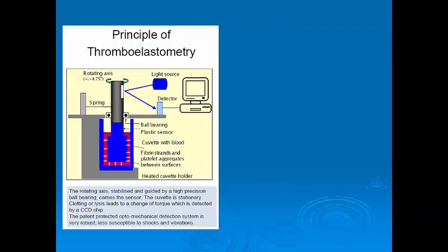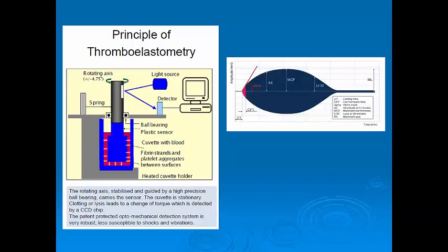A sample of the citrated whole blood is placed in a small cuvette. Reagents are added to activate the clotting process, and then a rotating pin is immersed in this sample. Over time, a clot forms, then strengthens, and this increasingly impairs the ability of the pin to rotate. This impairment to rotation is detected and displayed as a graphical image of amplitude over time. This image is called a temogram.